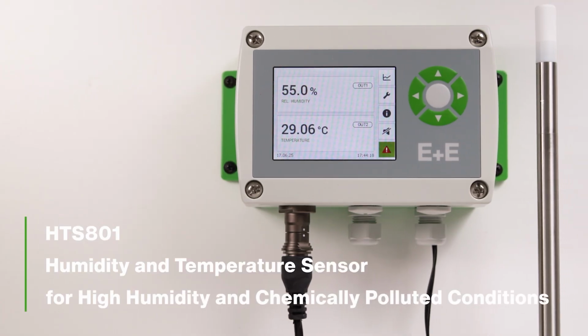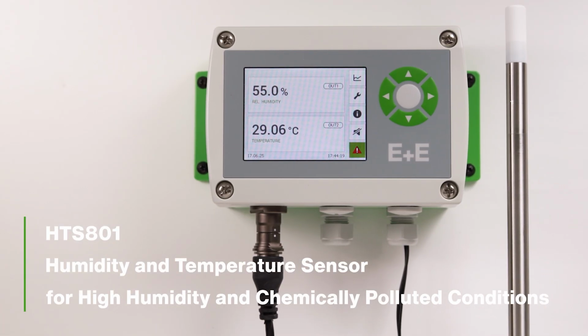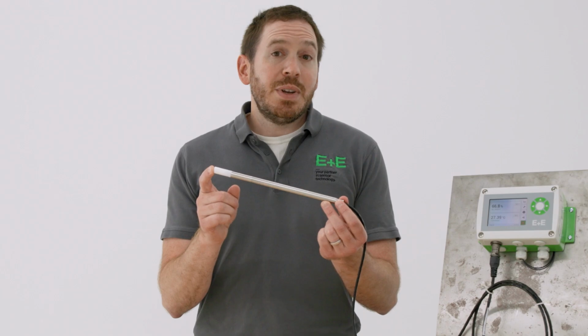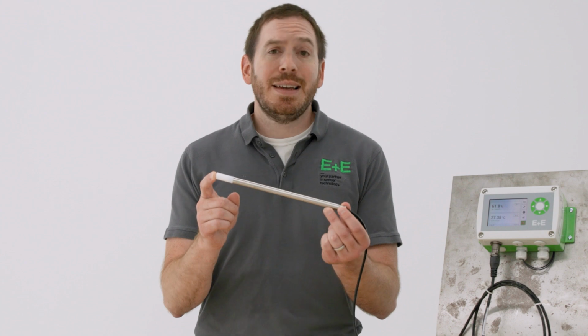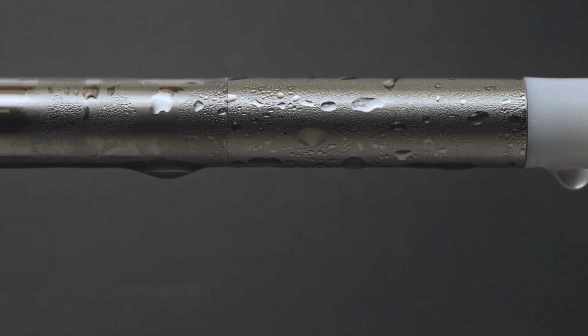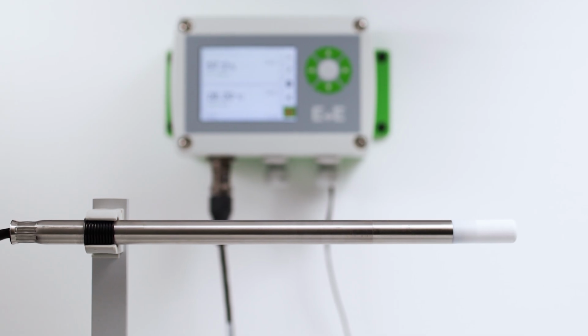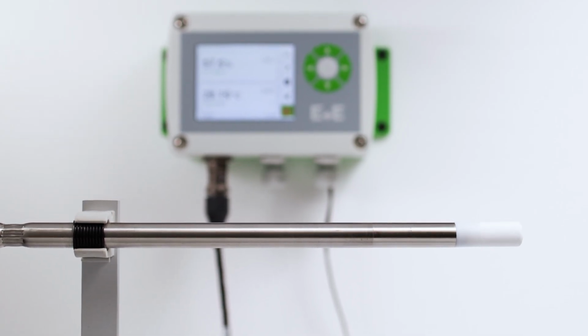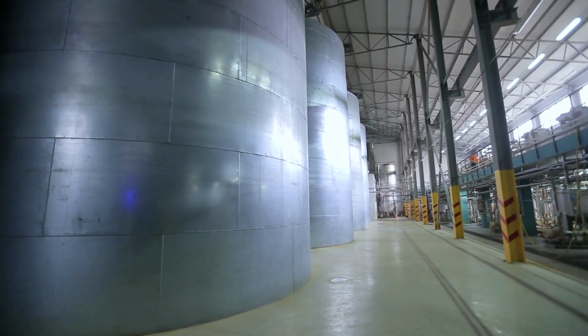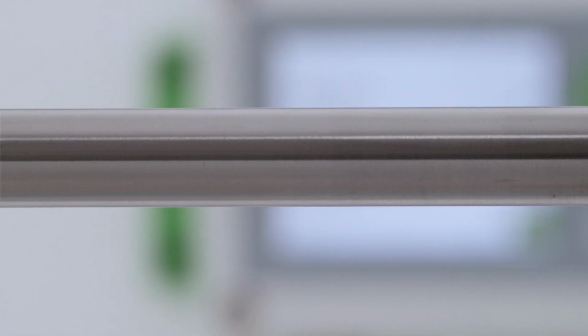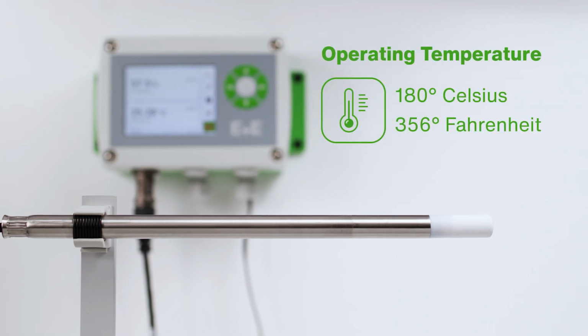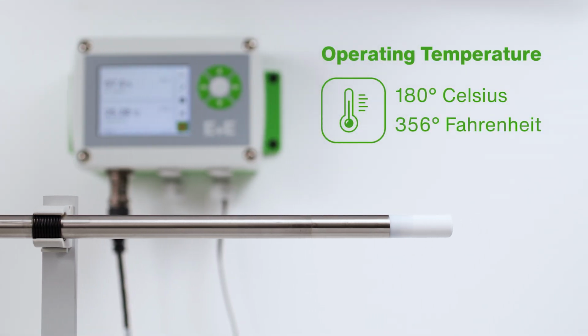This is the most robust humidity sensor in our portfolio. This is the humidity and temperature probe for the HTS-801. It is designed to operate in these high temperature, high humidity environments. First, the stainless steel probe contains high heat seals to ensure that it can operate within the industrial grade drying environment. Stainless steel will also not deform over time. This sensor is also designed to operate at high temperatures up to 180 degrees Celsius, which is 356 degrees Fahrenheit.